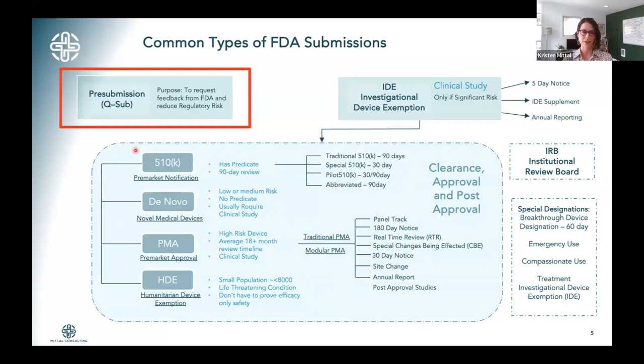One part of the preparation that's really important and used quite often is called a pre-submission. The purpose of a pre-submission in general is to request feedback from the FDA regarding questions you have, in advance of one of these submissions or in advance of an IDE submission. An IDE submission is an investigational device exemption, which is basically a request to be able to do a significant risk clinical study.